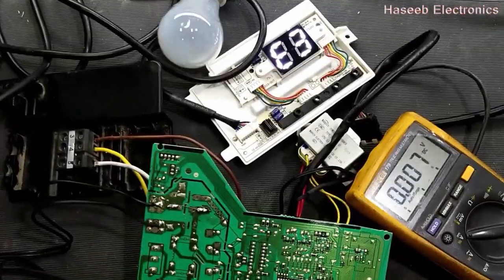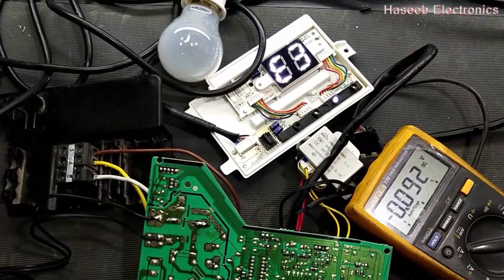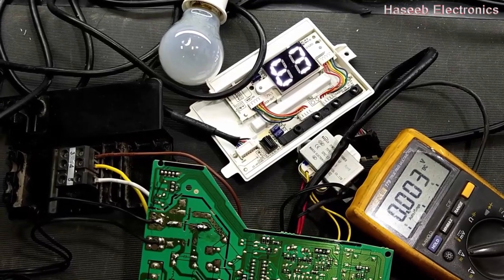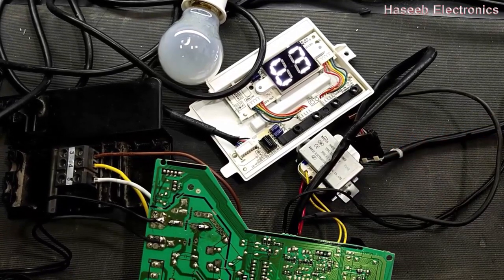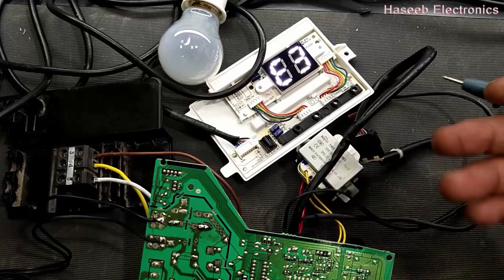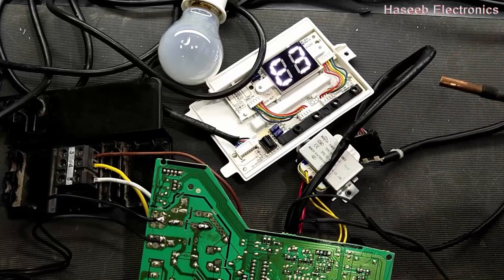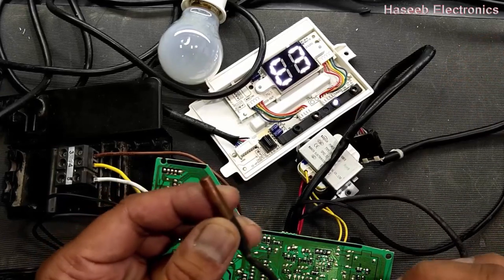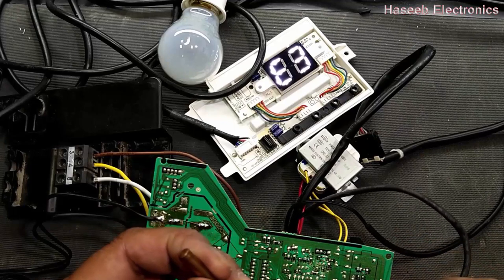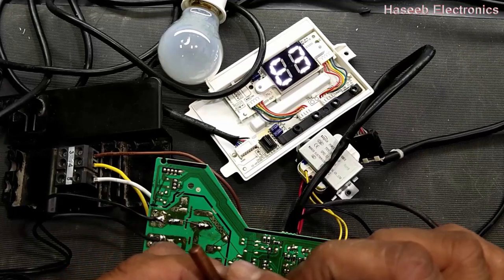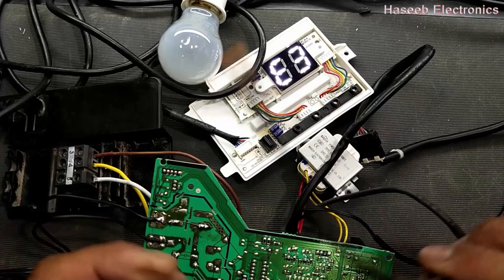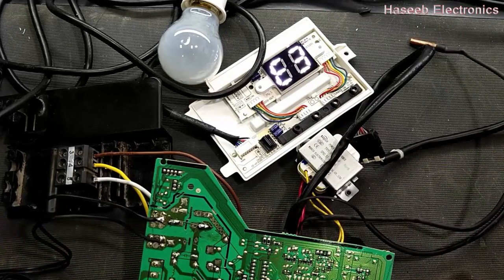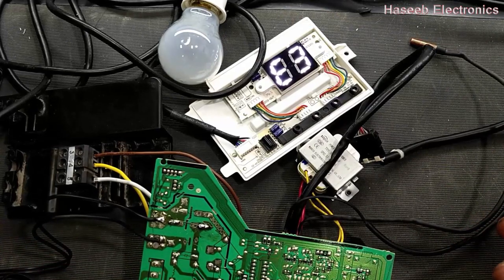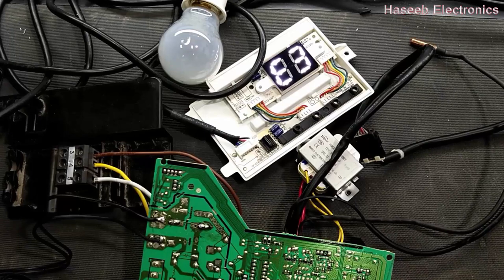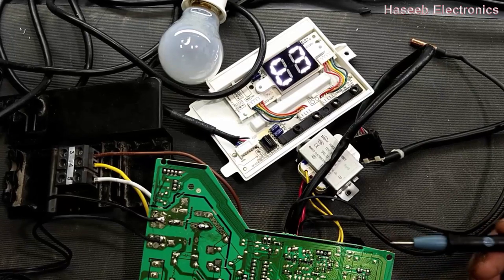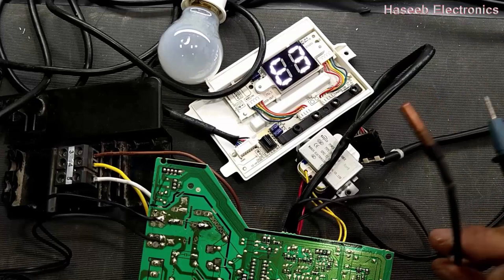And this time it is displaying an E3 error. Why? Because after running for a specific time, the pipe temperature sensor is not receiving any data, because we did not connect the compressor. So when the compressor is not connected, that means there is some error, some problem.